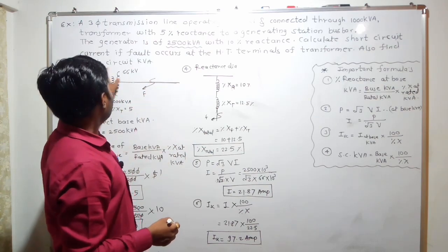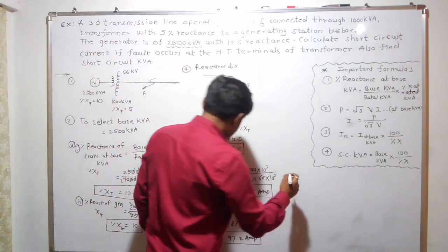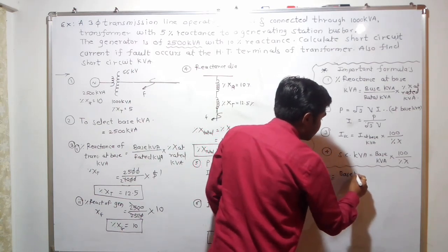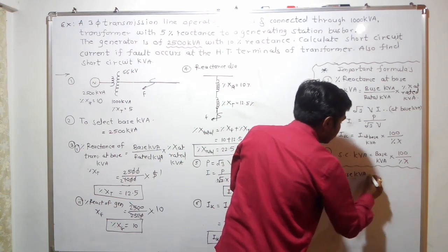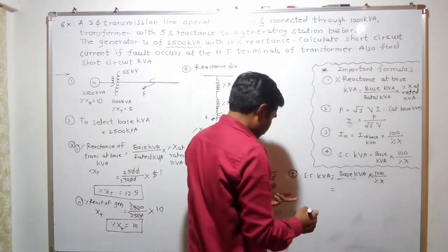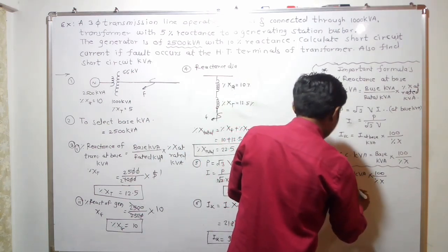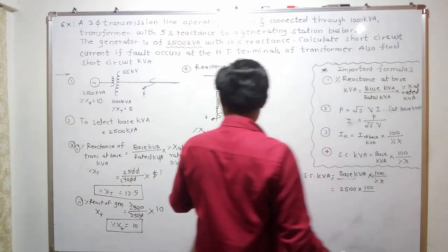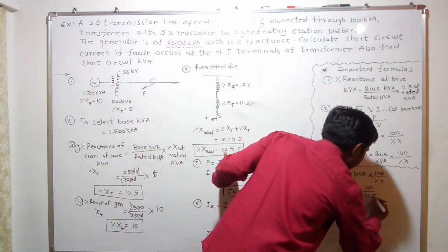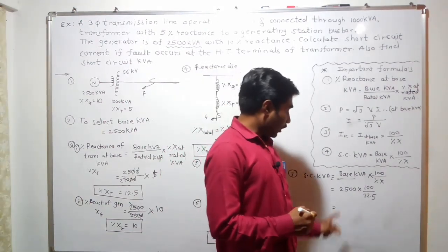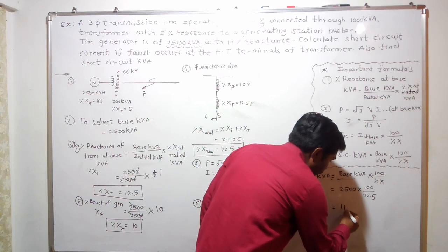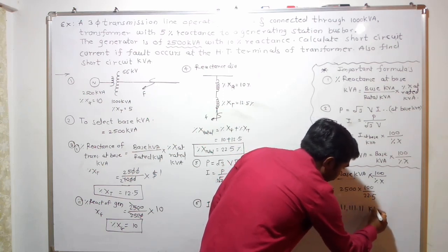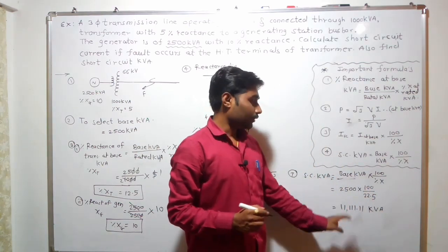The seventh step is to calculate the short circuit kVA. The formula is: short circuit kVA = base kVA × 100 / percentage X. Base kVA is 2500, and total percentage reactance is 22.5. So short circuit kVA = 2500 × 100 / 22.5 = 11,111 kVA, approximately 11.11 MVA. This is the value of short circuit kVA at the point of fault.